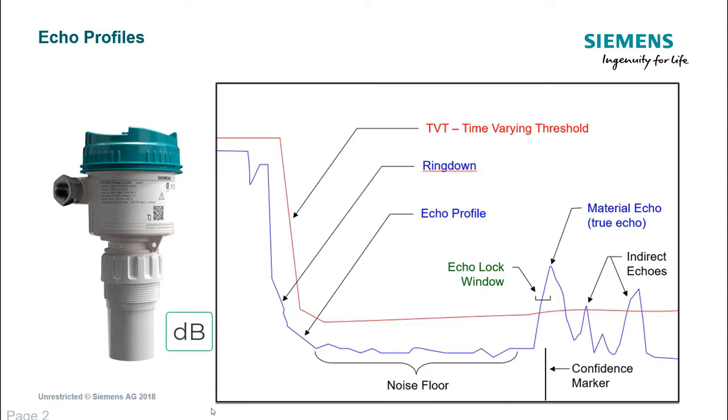Okay, so what happens then, it's easy to understand with sound. The signal travels through the air, this clicking sound that you can hear from an ultrasonics transducer. It hits an object, either liquids or solids. It reflects that back off, so it's like an echo, and then it comes back to the transducer. So we then get a signal, and that's a signal going vertically. It's not perfectly straight going up. Depending on the technology, it will be narrower, which you'll see as we go through this presentation.